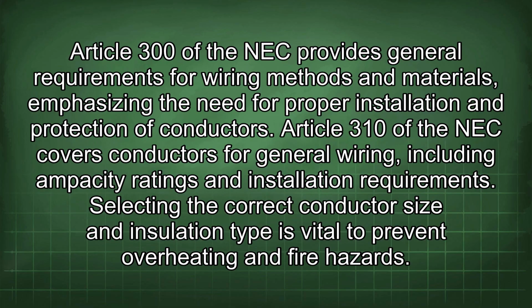Article 300 of the NEC provides general requirements for wiring methods and materials, emphasizing the need for proper installation and protection of conductors. Article 310 of the NEC covers conductors for general wiring, including ampacity ratings and installation requirements. Selecting the correct conductor size and insulation type is vital to prevent overheating and fire hazards.